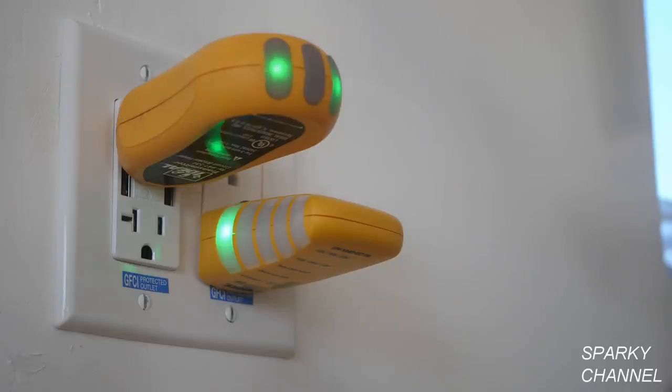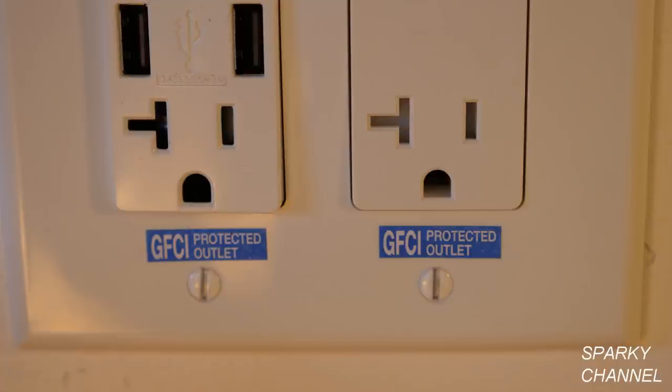And here's the GFCI test. I'm going to press the test button on the GFCI that controls those receptacles. And I press the reset and they come back on. So both of these receptacles have earned their GFCI protected outlet stickers.